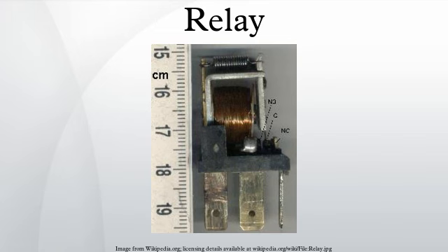Changeover, or double throw, contacts control two circuits: one normally open contact and one normally closed contact with a common terminal. It is also called a Form C contact or transfer contact. If this type of contact utilizes a make-before-break functionality, then it is called a Form D contact.